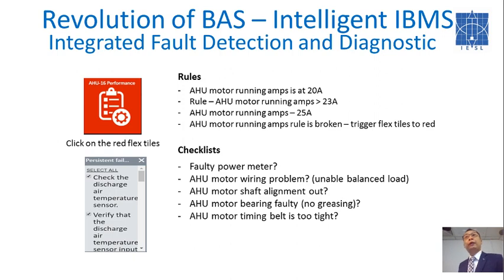Okay, without the IFDD, if your AHU is running on 25 amps, what will happen to your motor? Any guesses? Alright, your AHU motor itself will burn out. Burn out, worst case, you change the motor. But what if it doesn't only burn out, it catches fire? Your building will be on fire. So that's why IFDD also takes care of the safety and comfort of your tenants.